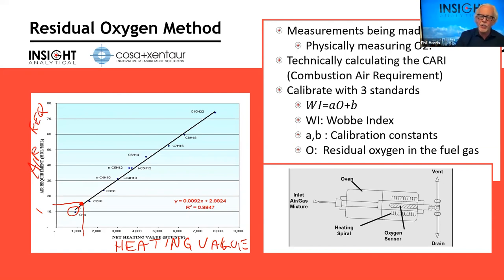It's a heavier hydrocarbon, and it ends up someplace up here, let's say, 2700 BTU fuel. We say, well, I've got to add 27 or 28 units of air for every mole of that fuel, or for every unit of that fuel that goes in. Put a cubic foot of that fuel in, I've got to put 28 cubic feet of air in with it. So this measurement allows us to figure out how much air we need to add to the burner to get the best burn of that fuel.